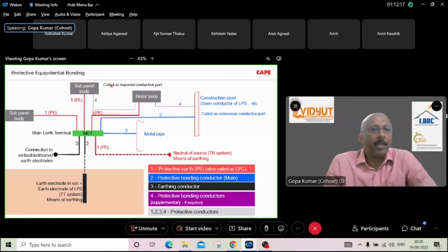This has been written not now. This has been written in all our standards since probably 40, 50, 60 years. But I always ask my clients, can you show me one metal pipe, let's say, for example, in a five-star hotel, the firefighting sprinkler metal pipe which is running all around the building? Can you show me one connection with a small piece of wire, let's say a 4 square mm wire, to the common bus bar? Most of the cases, it's quite unfortunate that these simple safety measures are not followed.